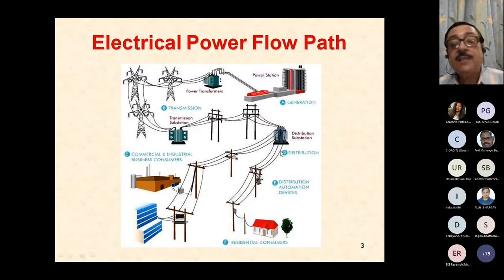Now, this part is called the low tension supply system, or the LT system, typically a three phase four wire system, so that domestic consumers can avail of single phase supply. Our distribution supply is nominally rated at 400 volts, so that line to neutral becomes 230 volts. And the primary distribution system can be 11 kV or 33 kV, depending on the application. The transmission, of course, is at still higher kilovolts, so that you can make a trade-off between the size of conductor and the cost of insulators. That's what decides. And so the higher the voltage, the lesser is the current.